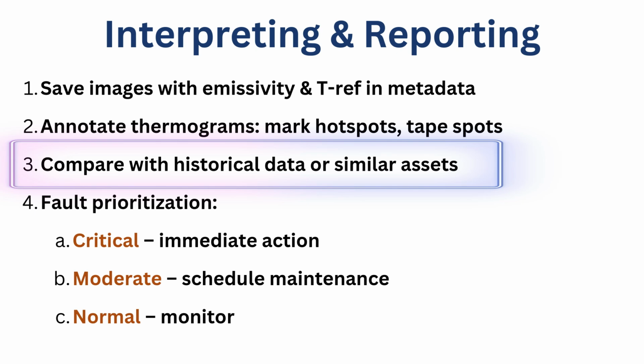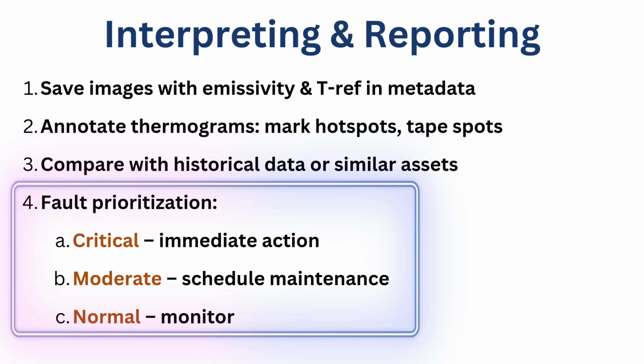Once the inspection has been done, then definitely you have to mention the faults, that is, what abnormalities you have found during your inspection. You should prioritize the faults basically in 3 sections. One is the critical one. Once you highlight any fault as critical, that means they have to take immediate action.